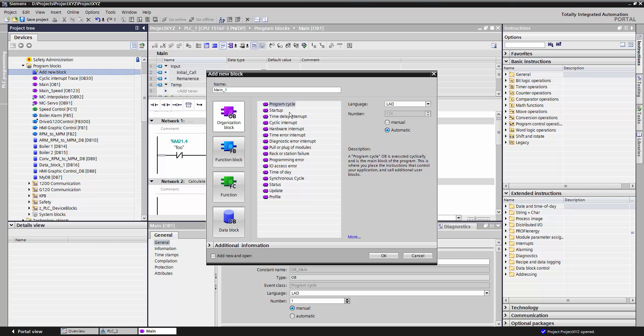An Organization Block can take on many forms. The most important is going to be your main routine, otherwise known as OB1. This is where most of your code will originate from.